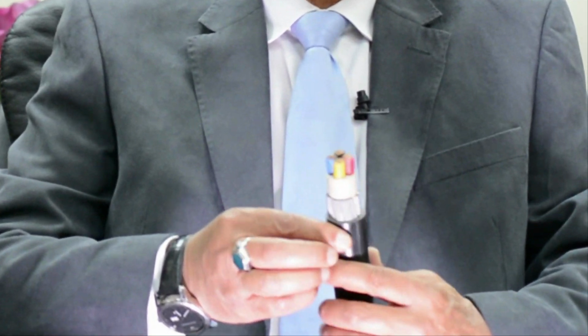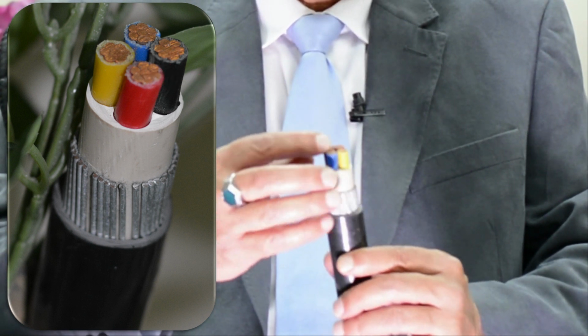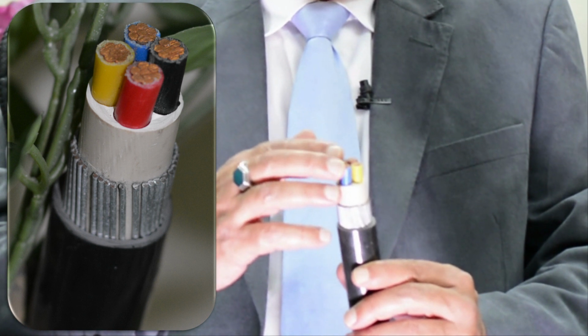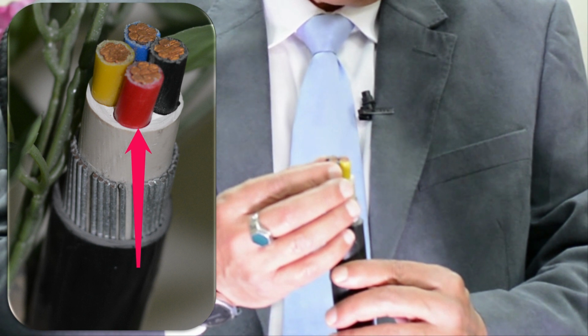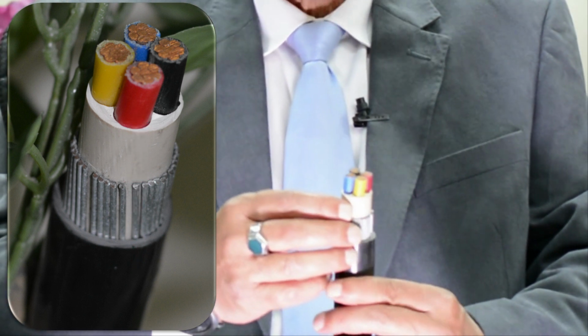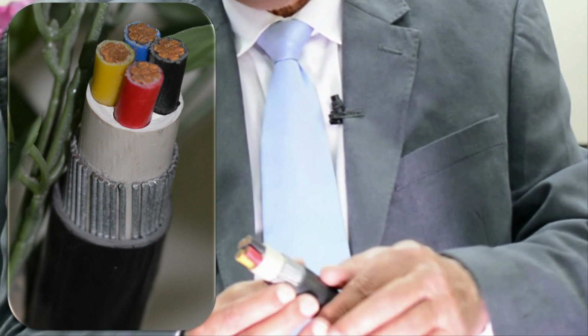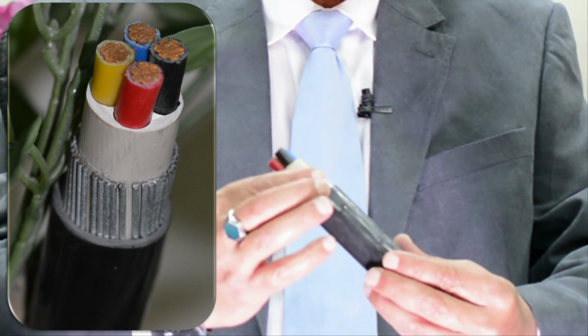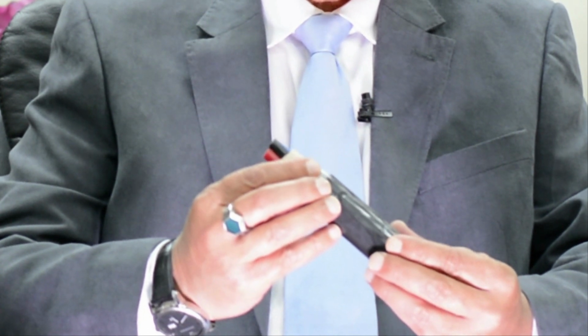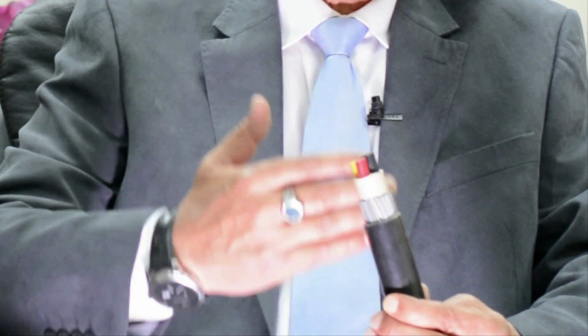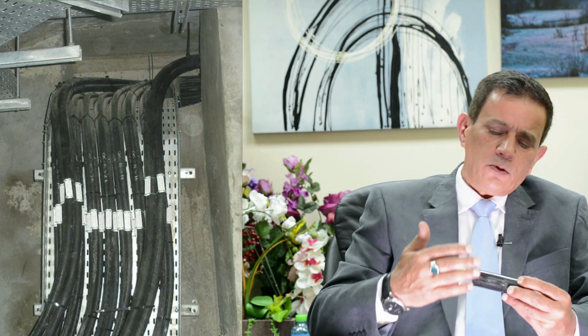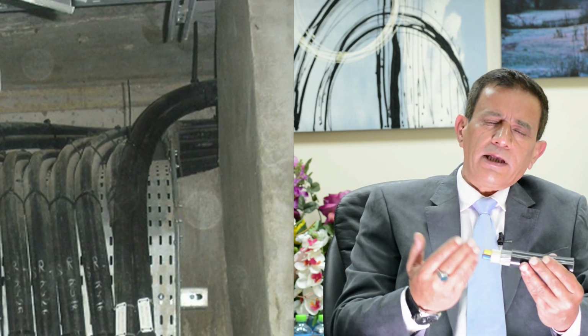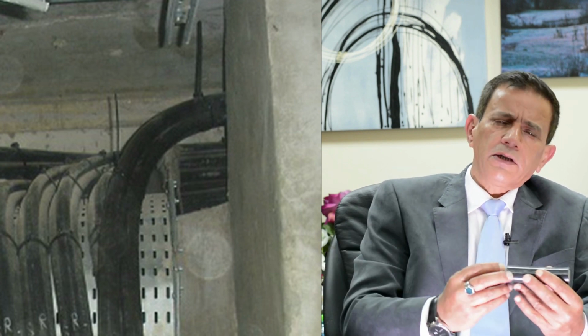For example, if we take an electric cable, this electric cable has the conducting element, which is the copper conductor. Sometimes it will be aluminum. And this copper conductor has an insulation, XLPE or PVC or rubber or any plastic material, and also another filler insulator. After that, there is steel wire armor. Steel wire armor is meant for mechanical protection. It's not supposed to receive or conduct current. So this insulator is acting as a separator between the current carrying conductor, the copper, and this steel wire armor. Also, this cable may be laid on a cable tray, which is metallic and can conduct current, but also this insulator with the outer sheet makes a barrier between the current carrying conductor and the containment, the cable tray housing or supporting the cable.